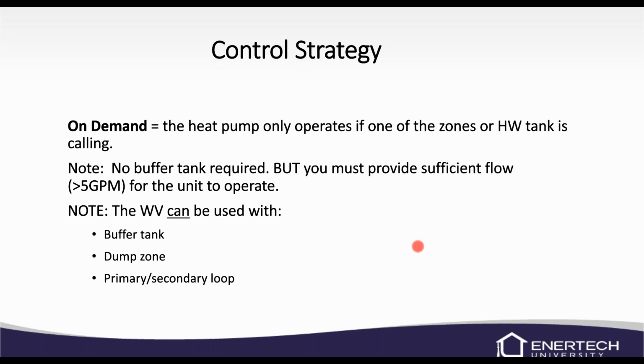So basically, there's no buffer tank required, again, but we've got to have proper water flow. The load and the source need to see 5 GPM to operate. Now, I'm going to tell you, it's actually about 4.5, but we're going to set up our flow for about 5 to give it a tiny bit of wiggle room, just a little bit of buffer there. You can also use it with a buffer tank, a dump zone, primary, secondary loop, a hydraulic separator. We will cover a little bit of the buffer tank hydraulic separator application because we're starting to go that route.